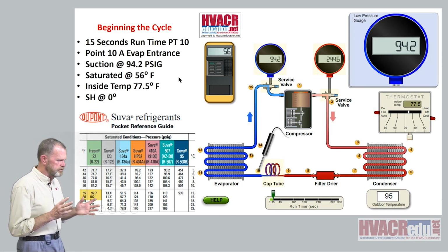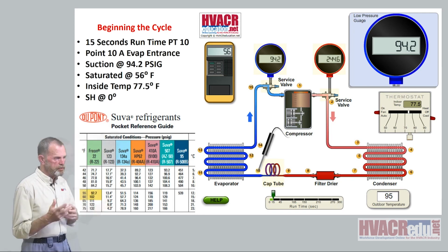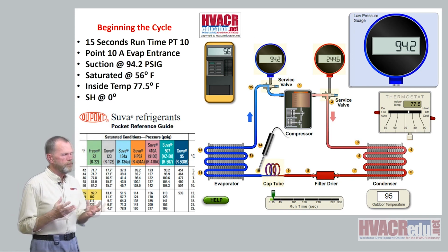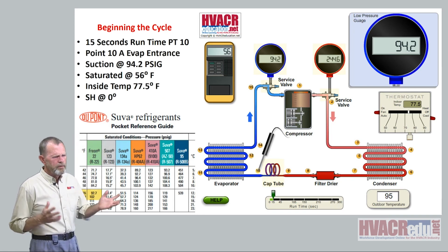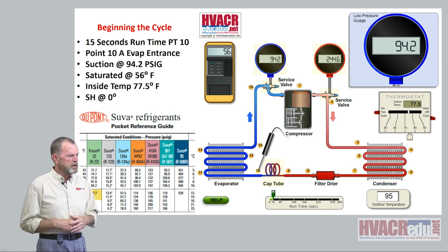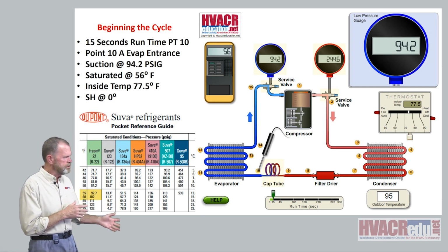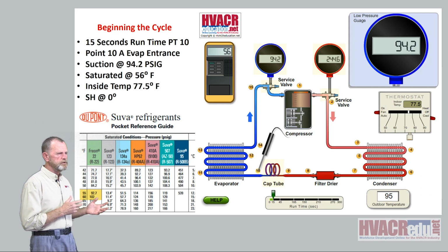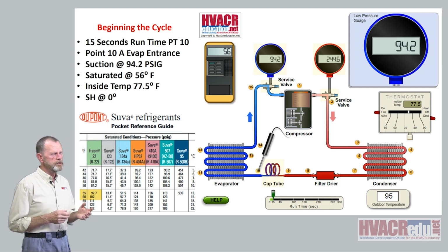When you walk in and look at a refrigeration cycle, if it's been running for a while, one of the things you want to know is, okay, so about where are we in the cycle? Did we just start? Are we halfway through? Are we getting close to pulling the load? What's happening? What's going on? Because that will tell you a lot as you're looking at it.